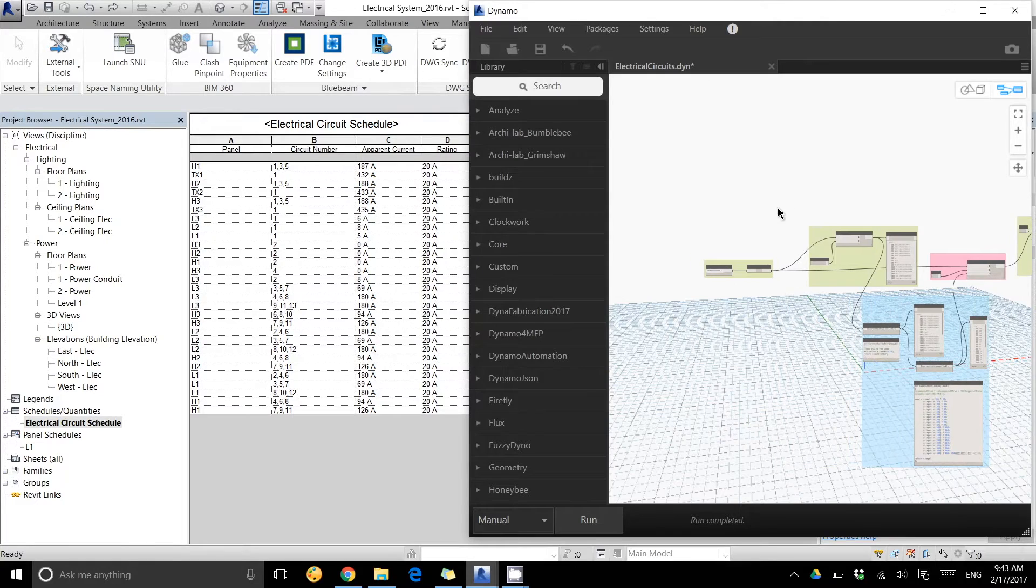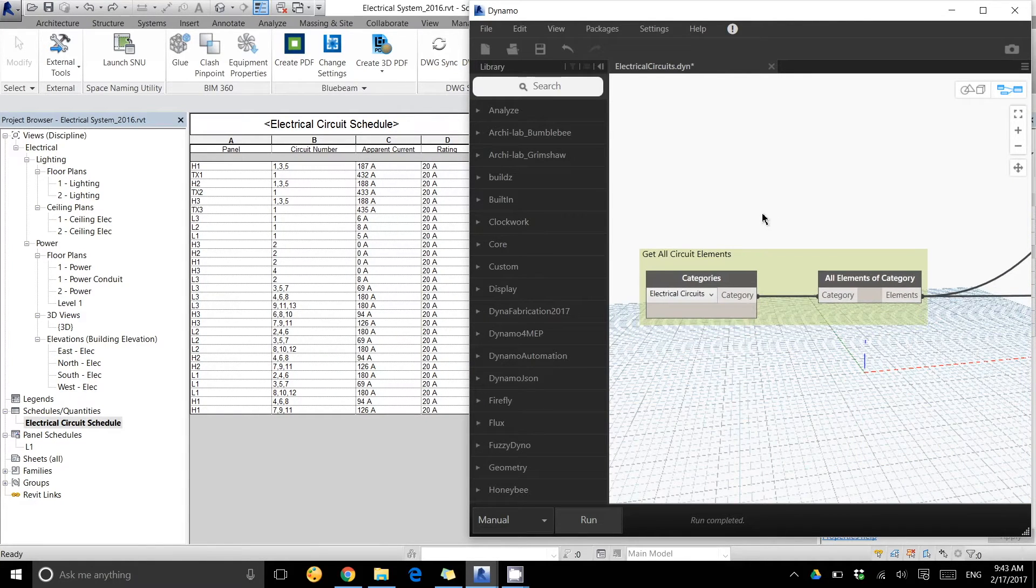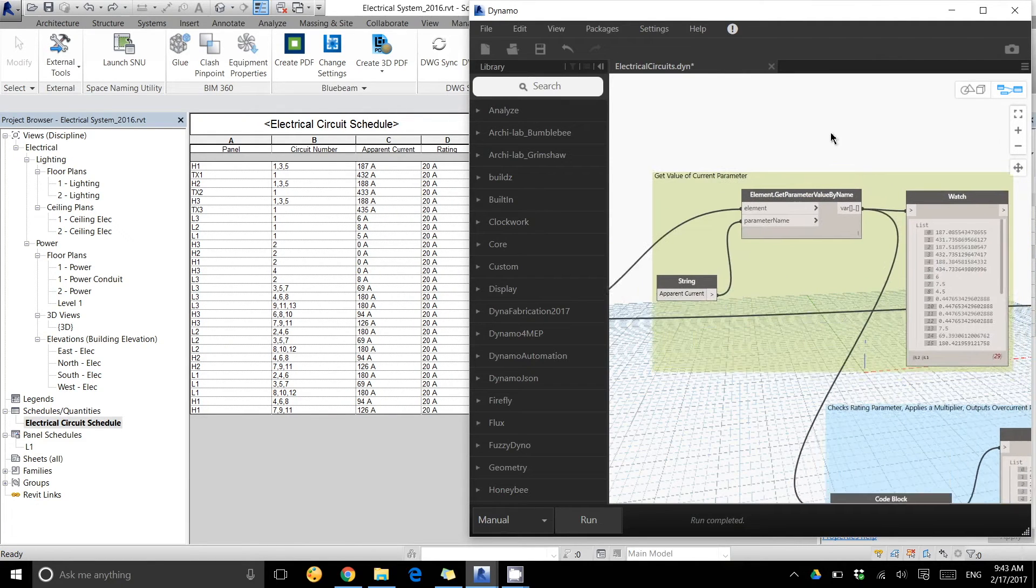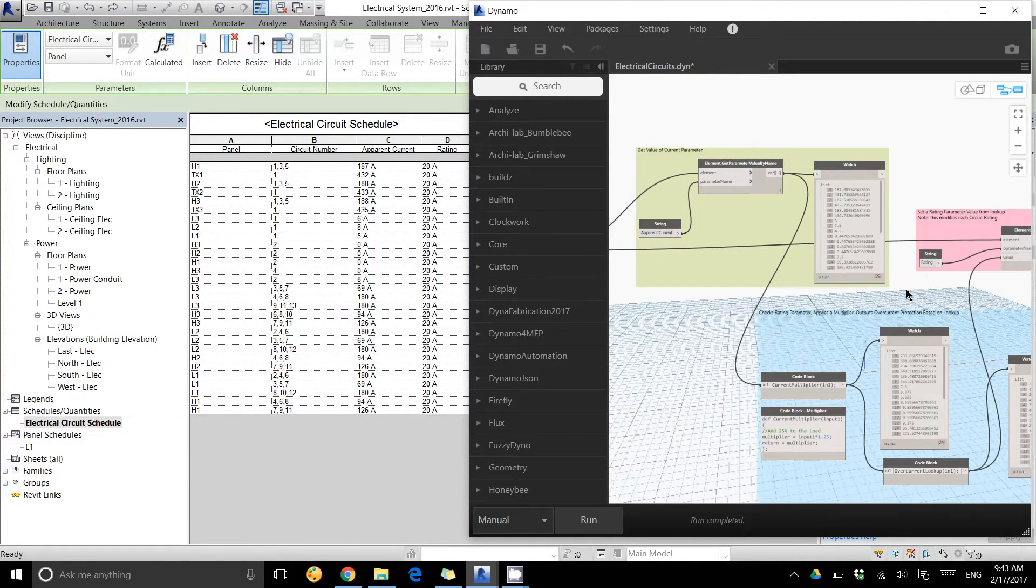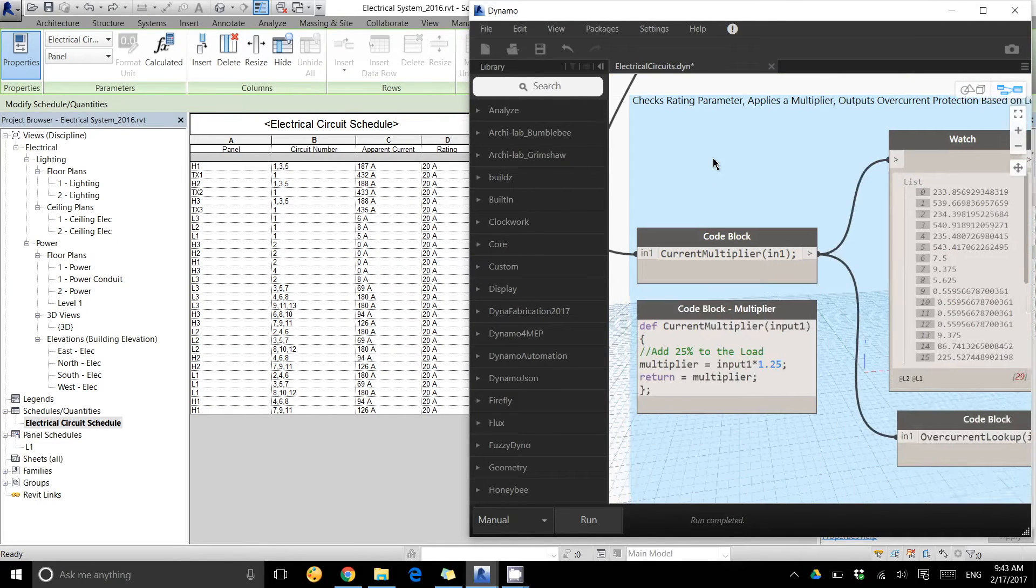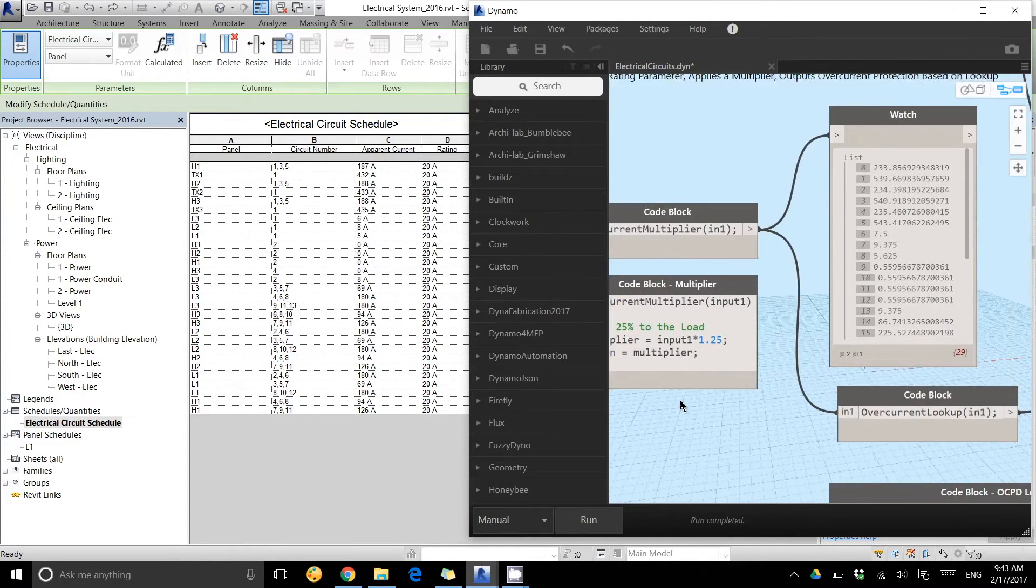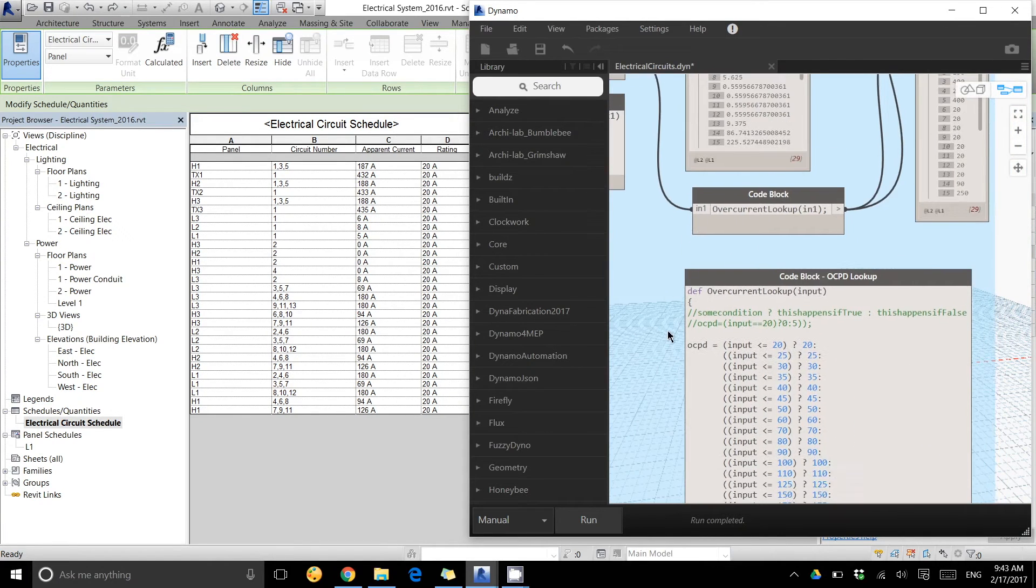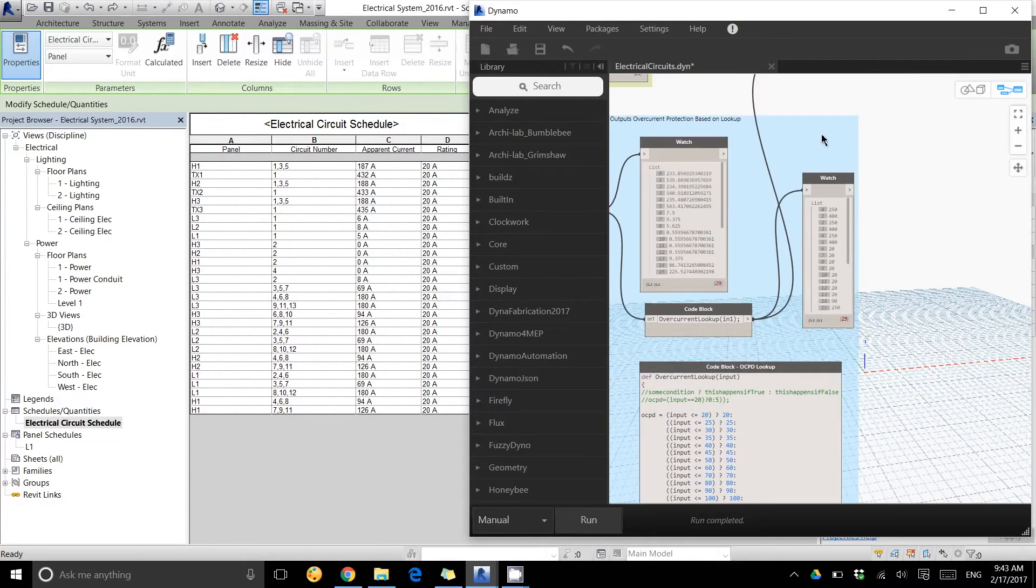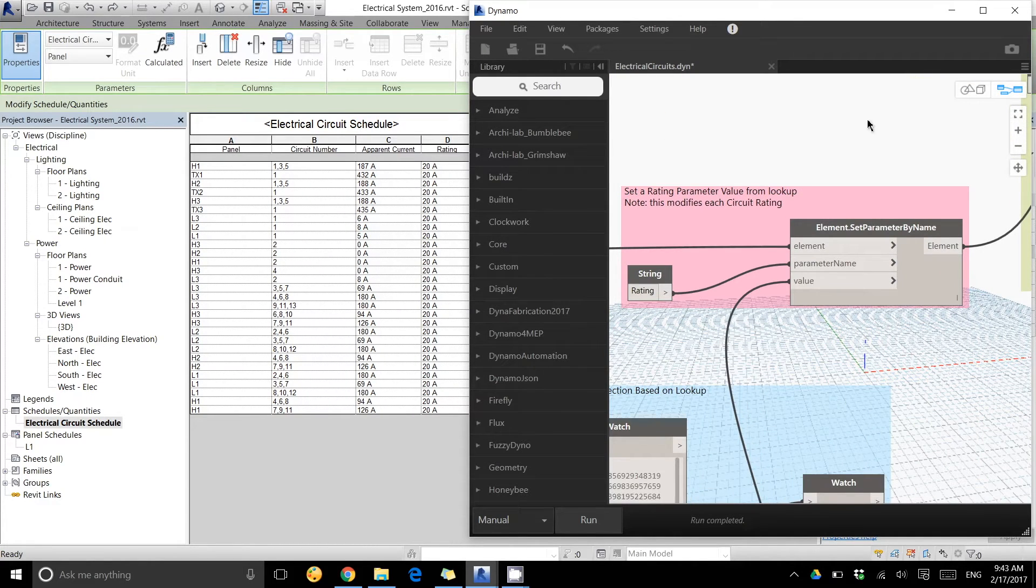The whole goal here is to run a script. Here's what I'm doing: I'm getting all the electrical circuits, I am getting the value of the current parameter, I'm doing a multiplier on that current parameter of about 25%, and then I am using this lookup table created in a code block to change the size of the rating or the overcurrent protection.